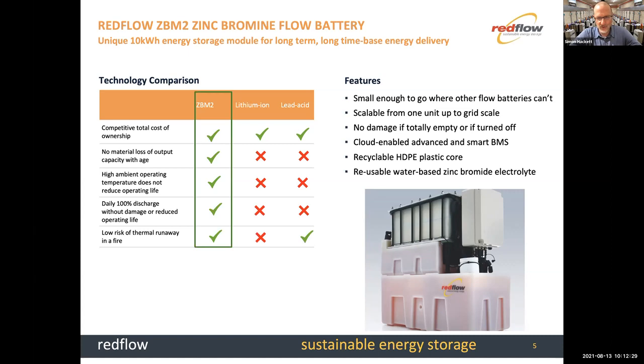If you look at the technology comparison chart on the left, the salient points about a flow battery are that the cost does wind up competitive, especially as we ramp volume up. We actually see ourselves chasing down the cost curve quite effectively. There's no material loss of output capacity with age with a flow battery, so as it continues to operate, you can expect to get the full output capacity every cycle as it ages. It doesn't care about operating in hot environments, it'll run up to 50 Celsius without any degradation to its function.